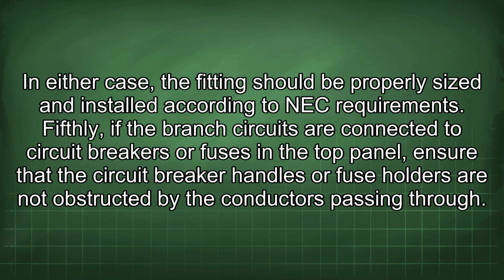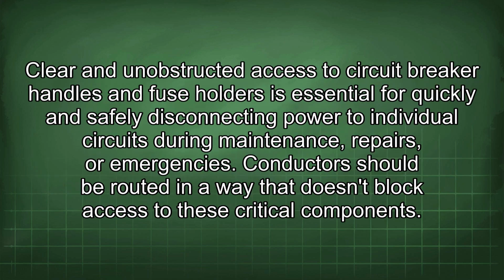Fifthly, if the branch circuits are connected to circuit breakers or fuses in the top panel, ensure that the circuit breaker handles or fuse holders are not obstructed by the conductors passing through. Clear and unobstructed access to circuit breaker handles and fuse holders is essential for quickly and safely disconnecting power to individual circuits during maintenance, repairs, or emergencies. Conductors should be routed in a way that doesn't block access to these critical components.